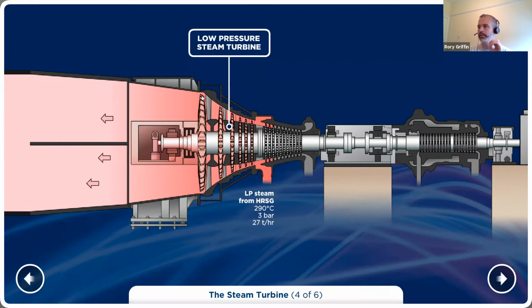And if that were to spin in air, you'd overheat the blades. So by spinning this in a vacuum, it helps cool the blades, but the best way to actually cool the blades is to get the steam through it. So steam at 300 degrees Celsius will actually act as a cooling agent on these blades.